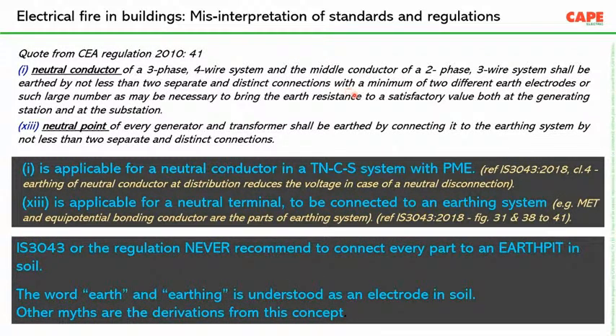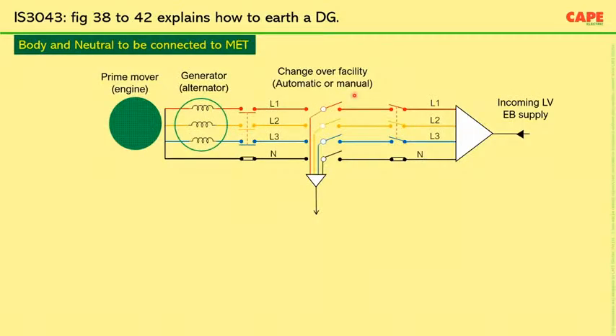Here, one of the problems which I see is whenever we hear the word earth or earthing, then immediately people think that earth means the earth electrode in soil. Actually, earthing has nothing to do, or very little to do, with the earth electrode in soil. I will show you the picture from IS 3043. The manual changeover of a DG and the electric supply. What you should understand is the electric supply considered here is a TN-C-S system.